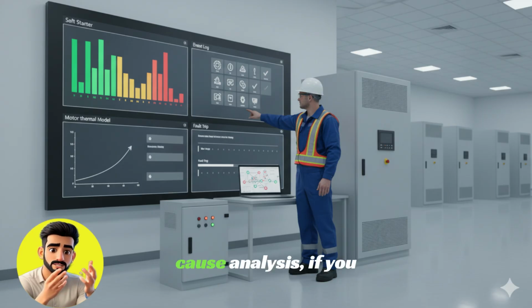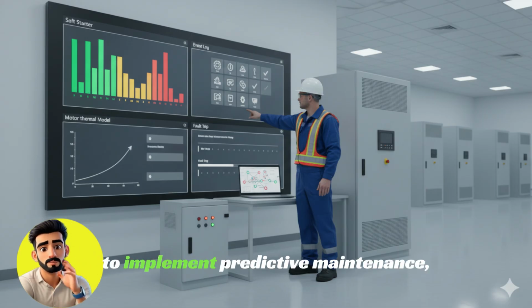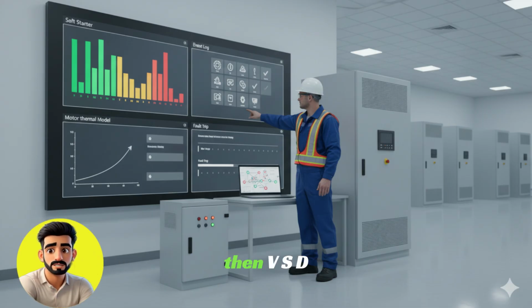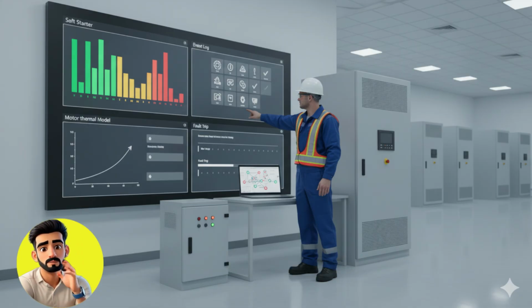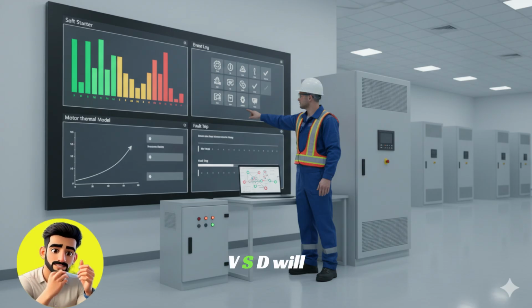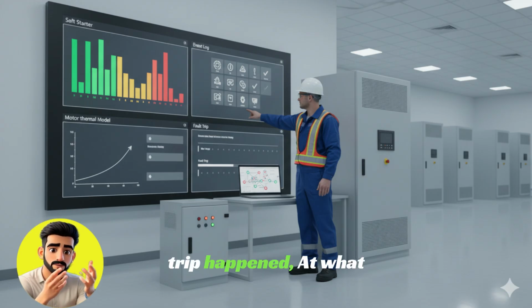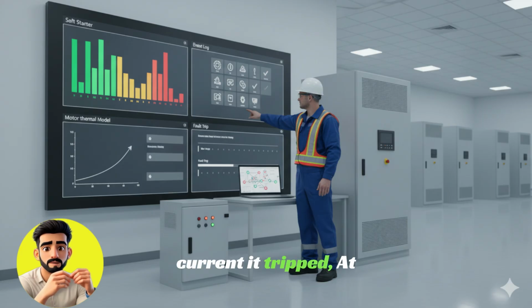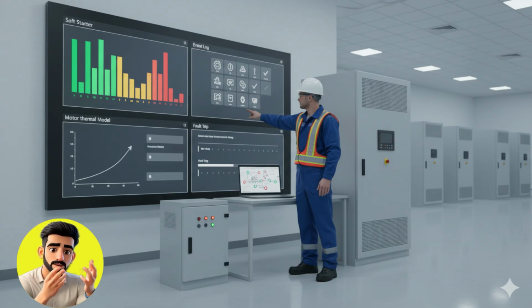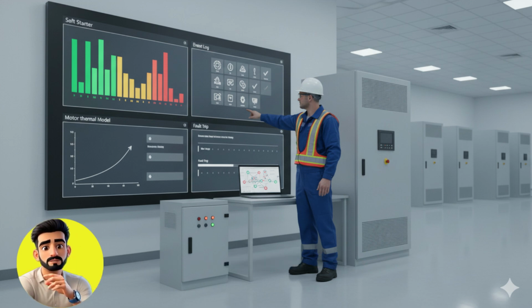If you like root cause analysis, if you want to improve plant reliability, if you want to implement predictive maintenance, then VSD becomes your powerful partner. Soft starter will normally just say, trip occurred, reset it. VSD will tell you when the trip happened, at what current it tripped, at what voltage it tripped, and under what condition it tripped. Here, the difference becomes very clear.